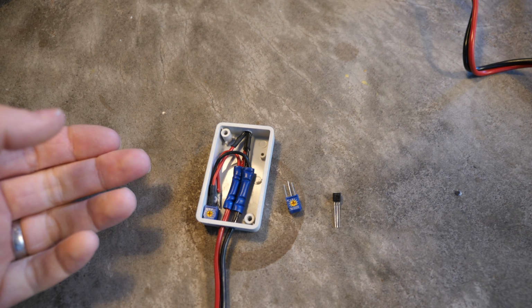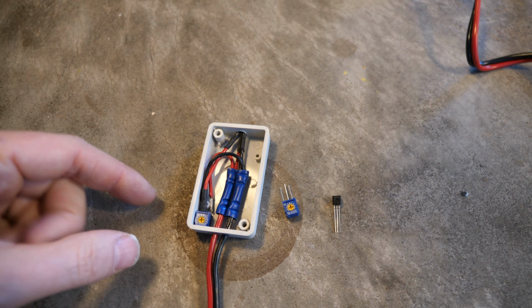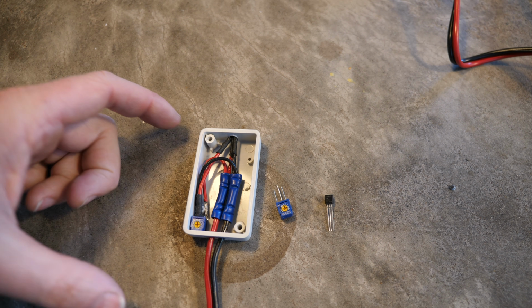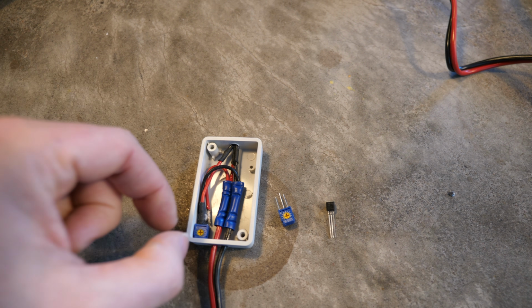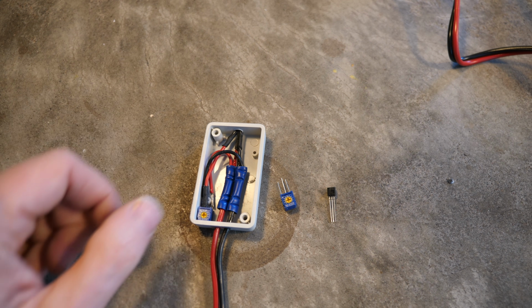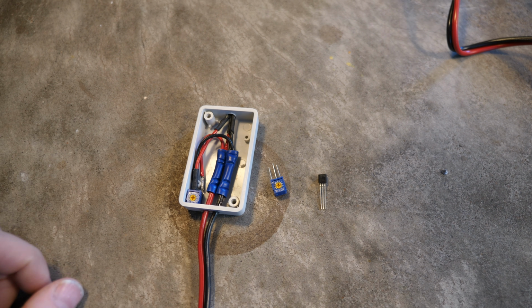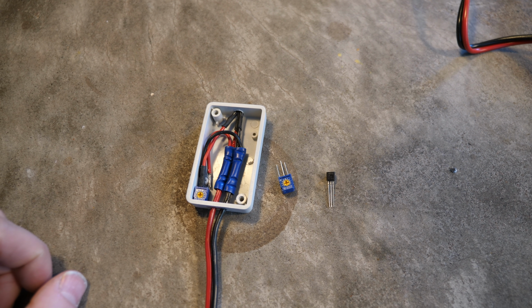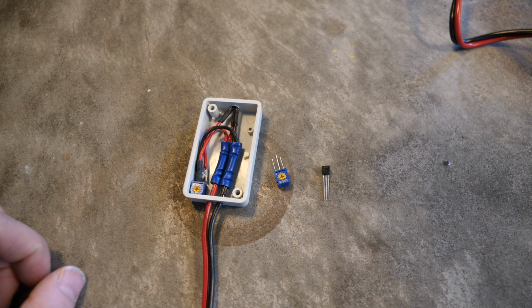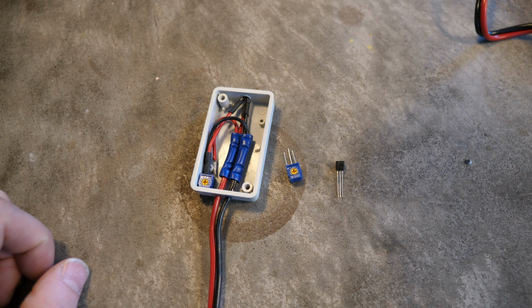So when I'm installing this, I'll take a comparison sensor that I know is good, compare it, and then adjust the potentiometer inside here so that it matches the known good sensor. Then it should be calibrated and we can install it in all the locations.